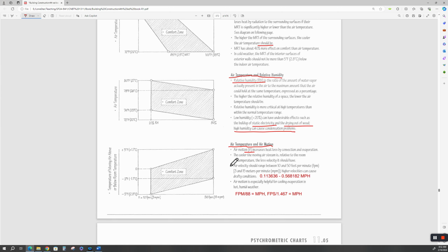Maybe I'm just being a geek this morning. All right, the cooler the moving air stream is relative to the room air temperature, the less velocity it should have. Well, that just makes sense, right? Air velocity should range between 10 and 50 feet per minute, FPM. If you're a metric head, this is in meters per minute. Higher velocities can cause drafty conditions.